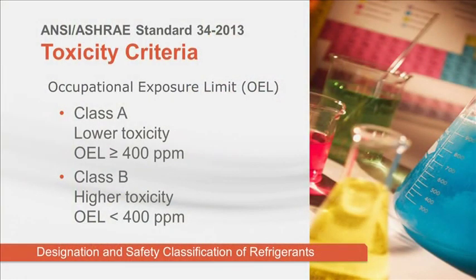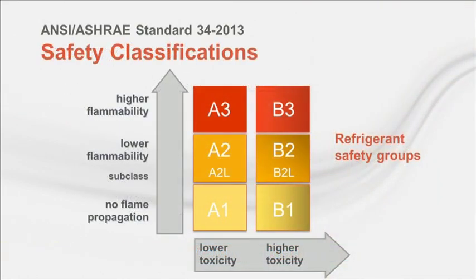The two levels of toxicity are defined using occupational exposure limit. The occupational exposure limit defines a refrigerant exposure level that is considered safe for most workers. Refrigerants with an OEL of 400 parts per million or greater are Class A. All others are Class B. So when combined, the safety classifications for flammability and toxicity yield the 6 safety groups shown. Most refrigerants used in VRF applications are classified as A1. That is, they are not flammable and they have low toxicity.